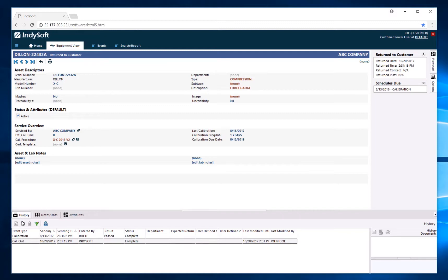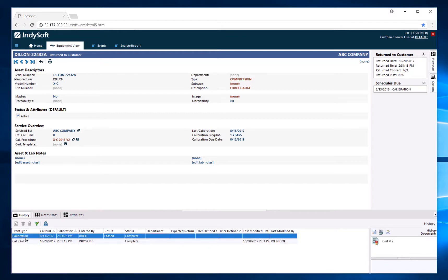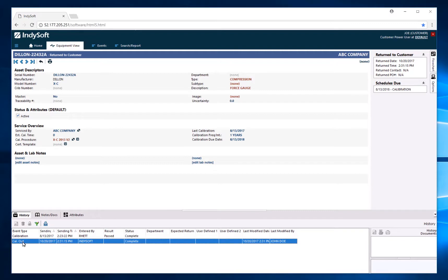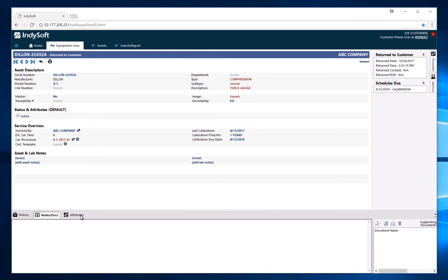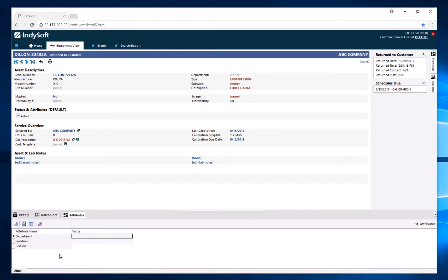Down at the bottom we have history, notes and docs, and attributes. You can now see a calibration event that has been applied to this asset, as well as the certificate in the right-hand corner. We also have an outsource calibration event applied to this equipment, so you can see any history for this asset. Under notes and docs you can see any notes in the system, and under attributes you can request or update fields depending on the rights set up by your company.